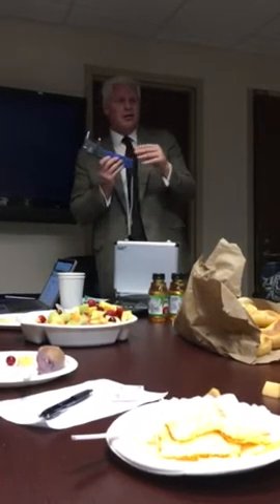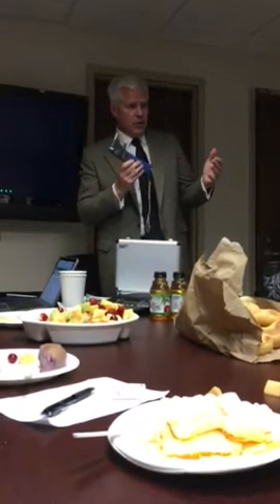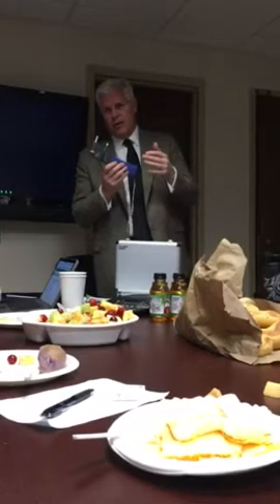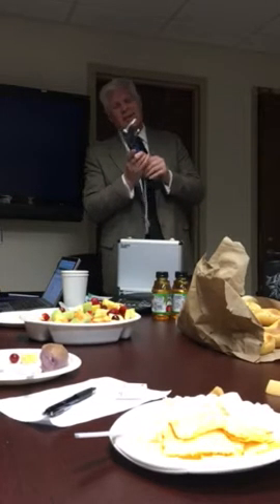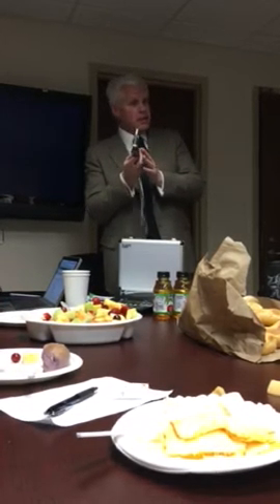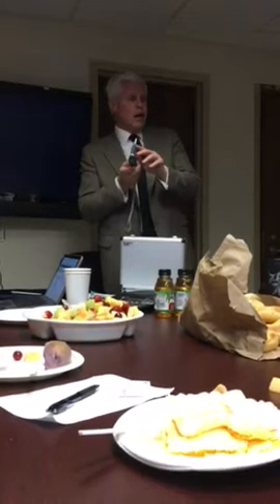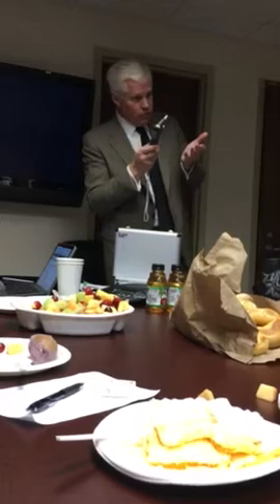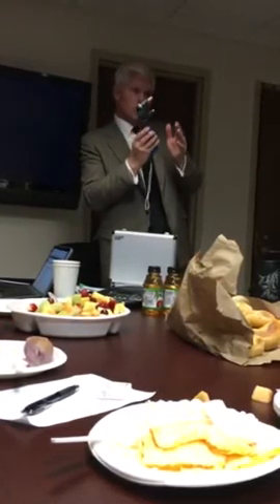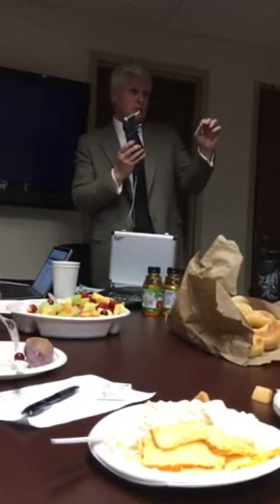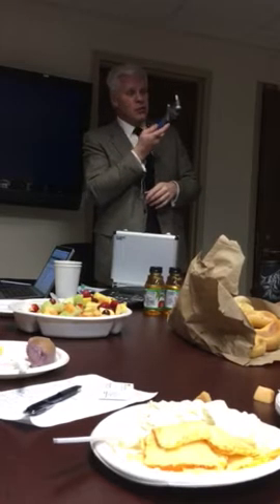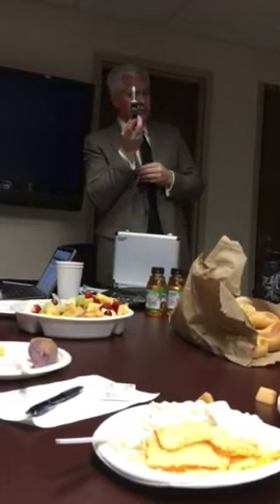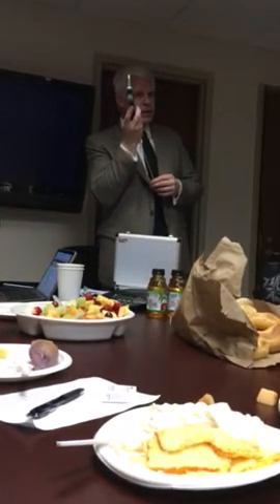And that chatter, some people would tell you that's our calibration. It's really not. We don't have to calibrate. Do you have to hold it up like that? Yeah, I suggest holding it up. I suggest getting in a habit of holding it up because after a while, this will lose magnetization, so it'll fall out on you, and you'll go to do it for the patient, or you'll go toward the patient, and it'll start to slide out, and it'll freak everybody out. So what you always want to do, if you hold it this way, you're not fighting gravity, and then you just hit that button, and then the probes magnetize them, okay?